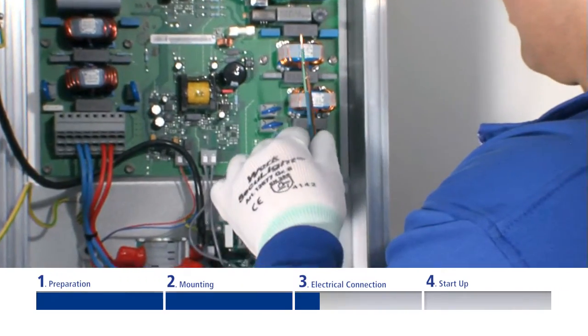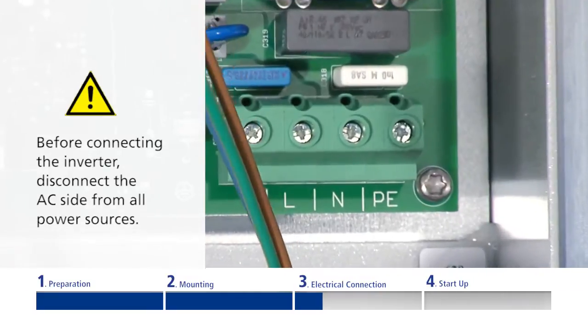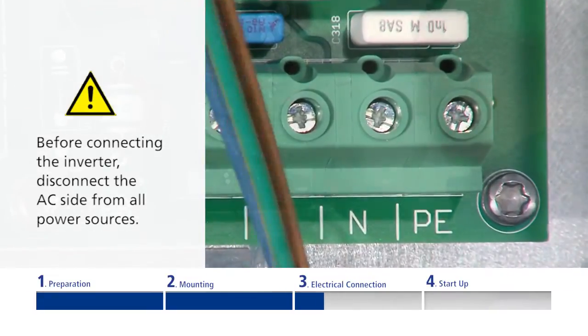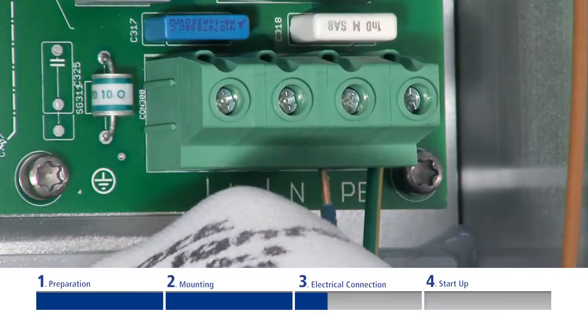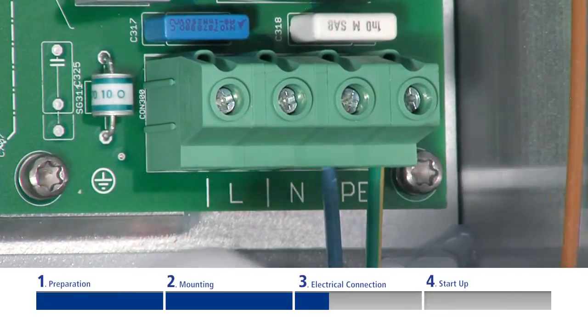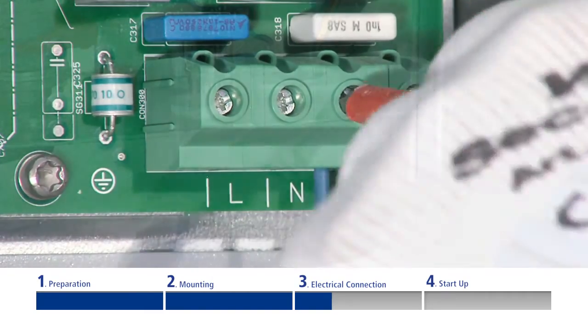After that, the AC inverter lead is connected. Strip the lead of its insulation and guide it through the cable fitting. Connect the leads according to the labeling on the PCB terminal. Check that the leads are connected properly and firmly. Then tighten the cable seal of the cable fitting.